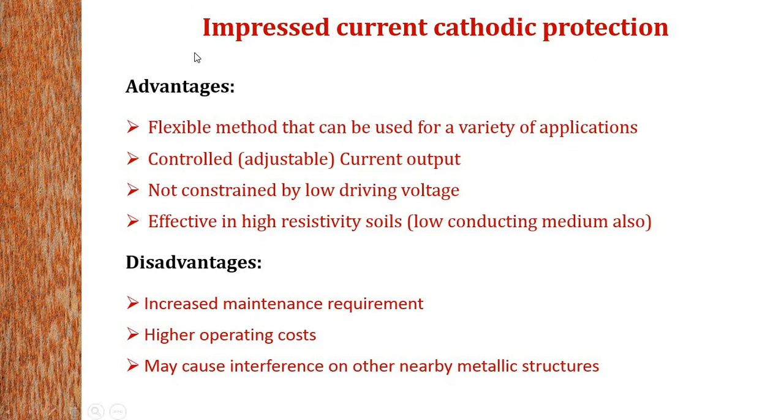There are some advantages as well as disadvantages of the impressed current method. This method is flexible because it can be used for a variety of applications. Current output can be controlled or adjusted. It does not have any constraint of low driving voltage. It is effective in high resistivity soils also. That means you can use this protection method even in less conducting soil.